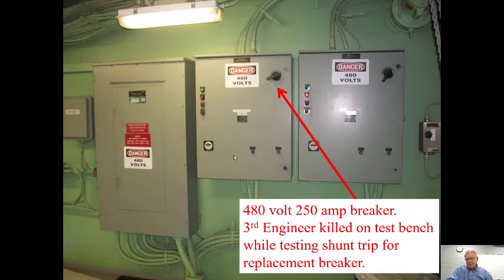Their third engineer was killed on a test bench while working on this breaker. You might think he got killed on that panel, but no—he had to change the breaker out. It's a sizable breaker, I'll show it to you when you come in for lab. It had what they call a shunt trip on it. You might think he was killed on 480, but no—he was killed with a little cheater cord hooked up to a 120 volt coil to test the trip. The hot wire came loose, and he reached out and grabbed it. You're on a ship, on a metal deck. He got electrocuted right there in the electric shop trying to test the 120 volt function of that breaker. The sad part was he didn't need the shunt trip—you just tape them off if you don't need it. He didn't know that; he was trying to test it to make sure.